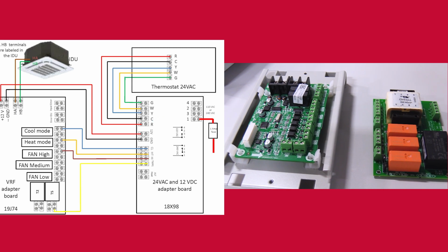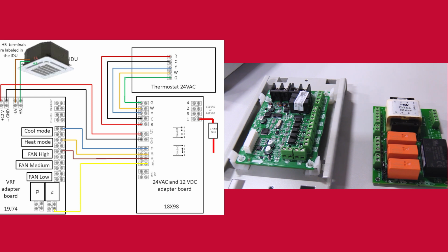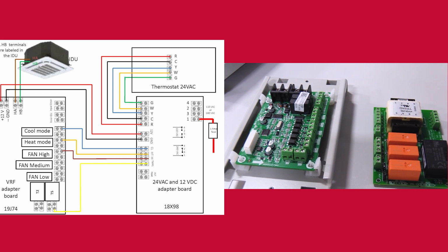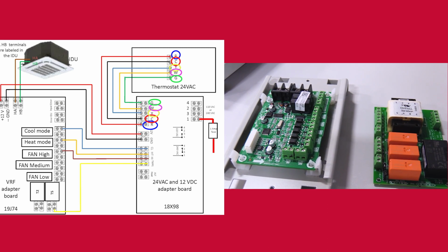Either one will work. Connect the 24-volt thermostat to 18X98. Connect R to R, C to C, Y to Y, W to W, and G to G.